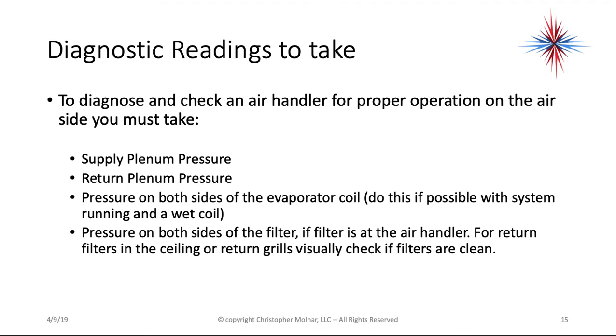To diagnose and check an air handler for proper operation on the air side, you must take supply plenum pressure, return plenum pressure, and pressure on both sides of the evaporator coil — try to do this with the system running and a wet coil. Also take pressure on both sides of the filter if it's in the air handler. For return filters in the ceiling or return grills, you may not be able to get a filter static pressure reading, so visually check them, and make sure the homeowner has not installed high-restriction 3M filters, because they are too restrictive and will cause problems.